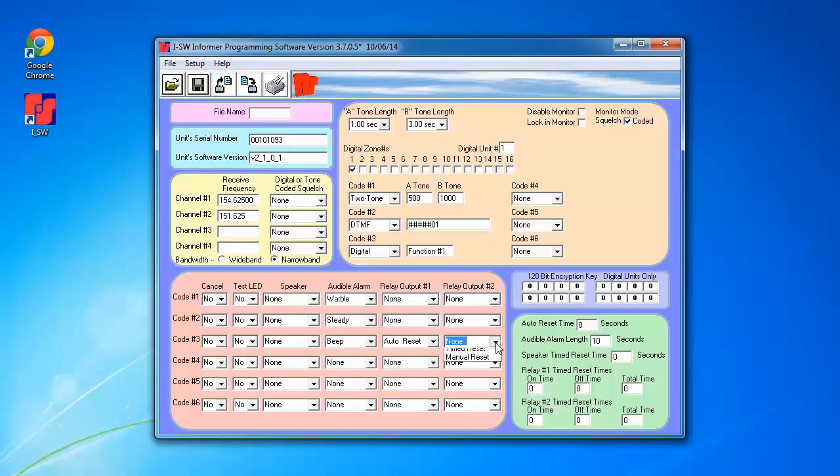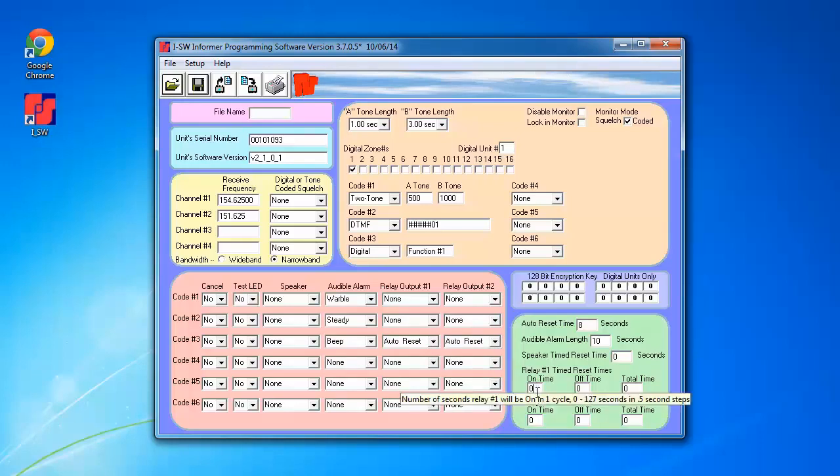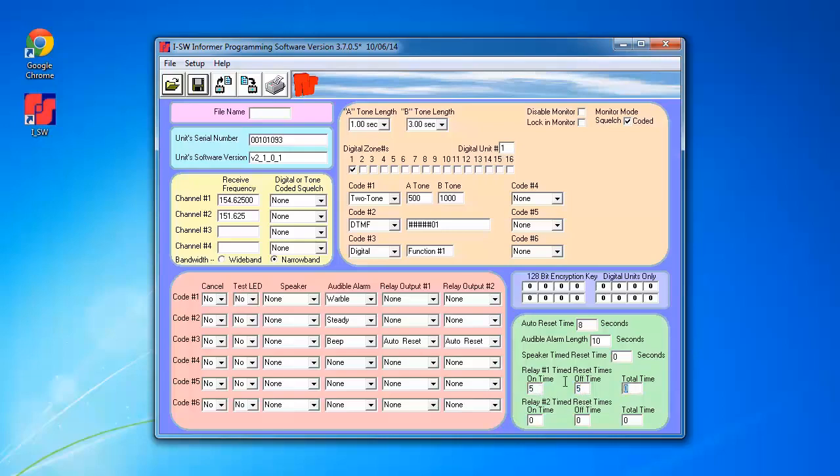I'm going to choose auto reset for both of these. For relay 1 on time, I'm going to use 5 seconds, off time of 5 seconds for a total of 10 seconds as an example. And I'm going to do the same for relay 2 as well.